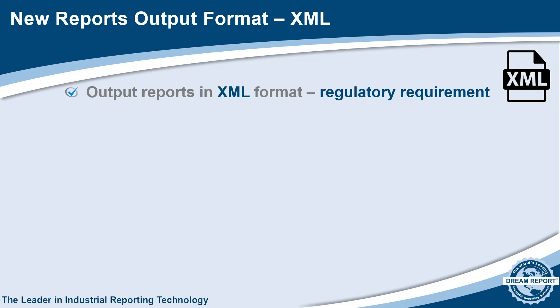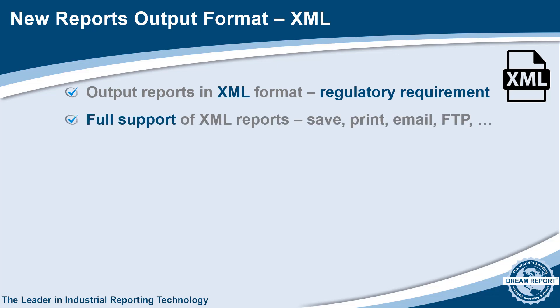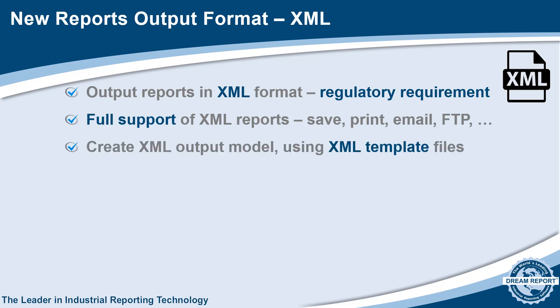In order to meet the regulatory requirements in several states of submitting water quality reports in XML format, DreamReport 5.0 now adds XML as a report output format, in addition to PDF, Excel, CSV, and HTML5. We've included full support for the XML output format, including saving to local or network drives, printing, emailing as attachments, and posting to an FTP server. Once the report has been configured, the XML output can be created from scratch, or you can import an XML template file — for example, as provided by the state — and then map the report objects and calculations into the XML document.